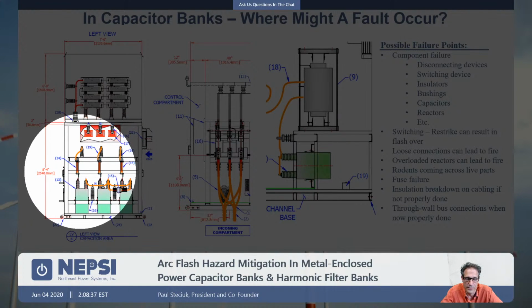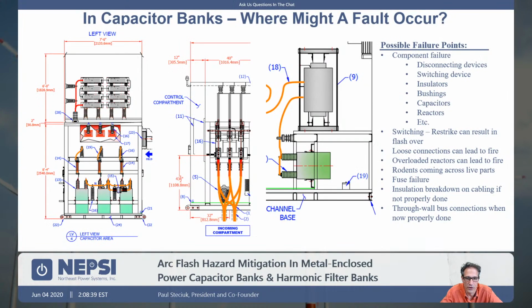We often see a possibility of fuse failure. Current limiting fuses are susceptible to failure due to overload. We use a SIBA blown fuse detection system. That SIBA blown fuse detection system helps to protect the fuse from overload. Current limiting fuses, especially at the medium voltage level, are susceptible to overload and failure. What happens is the fuse heats up and the sand drops out and it flashes over within the equipment. So we use a special fuse manufactured by SIBA. It has an overload thermal element built into it that shuts the system down should the fuse go into a overload condition, thermal overload runaway.